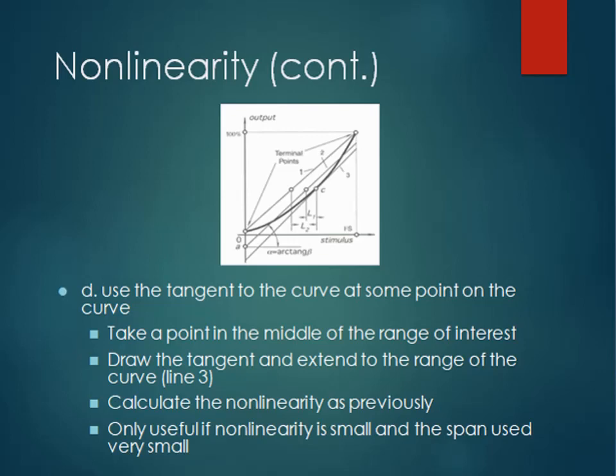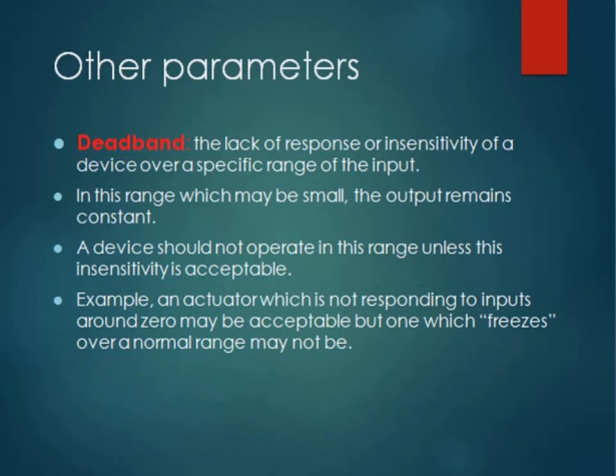And one more method is there: use a tangent to the curve at some point on the curve. Take a point in the middle of the range of interest, draw the tangent and extend it to the range of the curve, and calculate the nonlinearity as previously. It is only useful if nonlinearity is small and the span is very small.